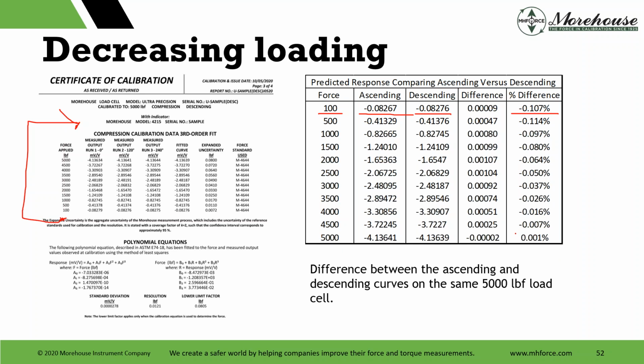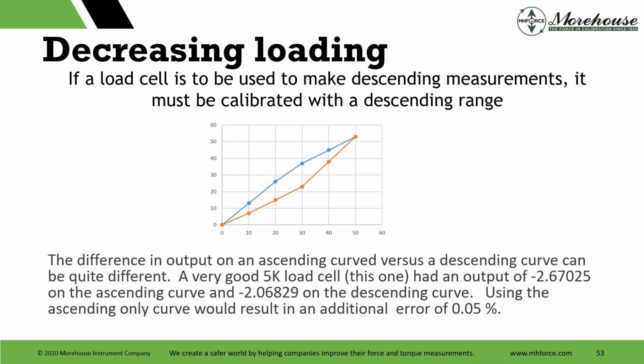We have to go back up to capacity to descend. So that's why you would have a slight difference, because we're using a slightly different curve and data set if we're fitting to the descending curve. So when we look at descending right here, we have these differences. So if a load cell is going to be used to make descending measurements, it has to also be calibrated in descending mode. And that's really the point.